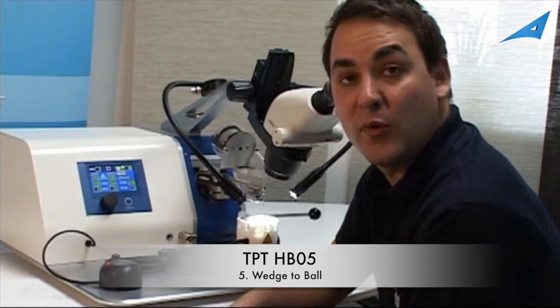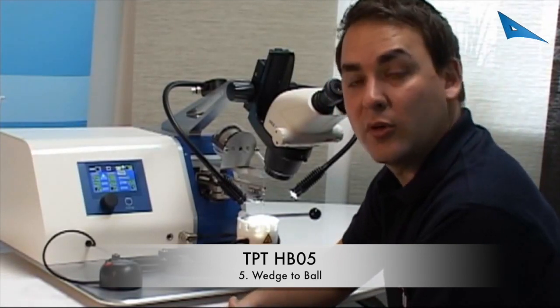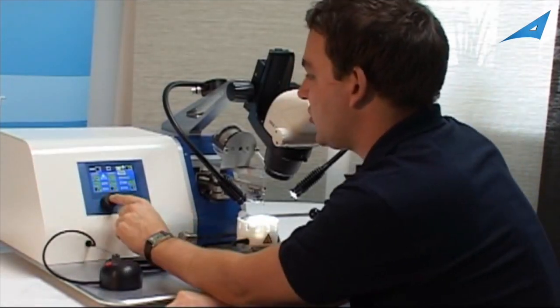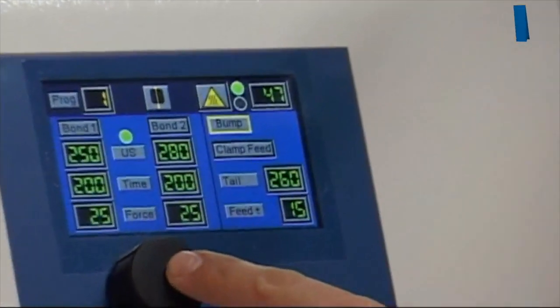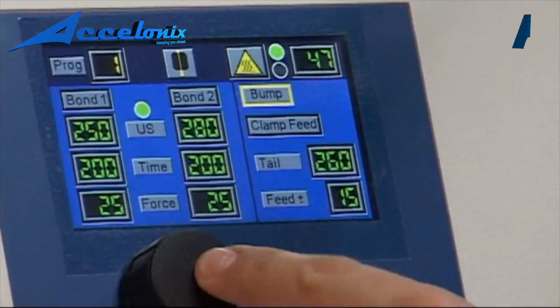If your machine is equipped with wedge and ball bonding mode, then you can easily change it by pressing this button. So you have wedge, ball, and bump bonding mode.